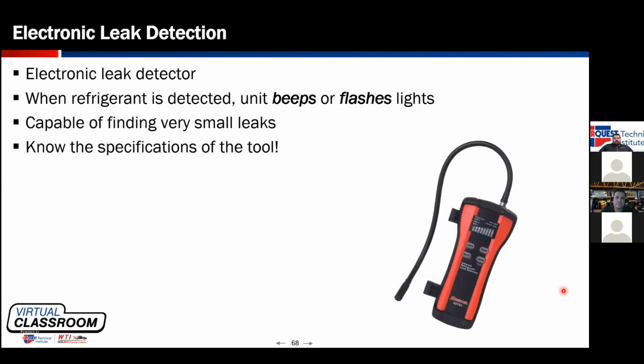So how an electronic leak detector works, so we said they're capable of finding very, very small leaks, and the detector will alert you to a leak with either an audible or a visual warning. You can see this detector has a light scale that, depending on how bad the leak is, it will start lighting more lights and the beeping will become faster. As I said again, know your leak detector, know what tool you are using.